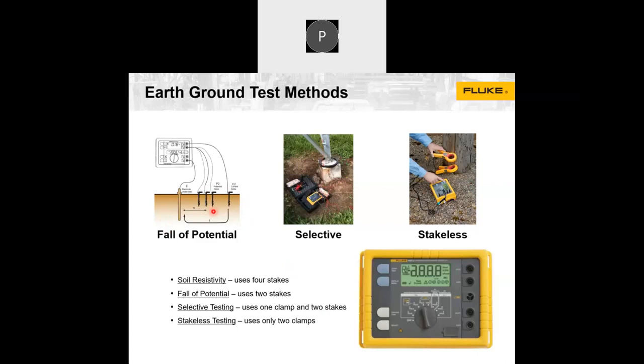For that, you need multiple stakes and a device that properly pumps voltage for this kind of testing. It pumps the voltage across 2 terminals, then measures the resistance between these two, or the potential difference between these two stakes, and then calculates the resistance. That's how earth testers work.